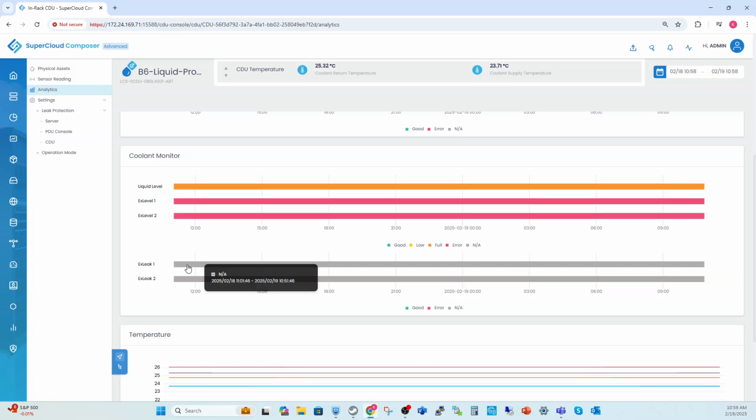If these leaks were ever detected at a rack level, SCC would have jurisdiction, report the action, and set the enforcement policy to shut down the entire rack itself based on the PDU, through us building our universal agent across multiple PDUs.